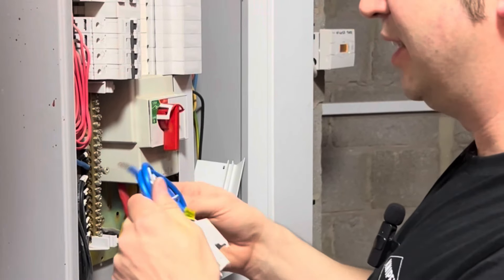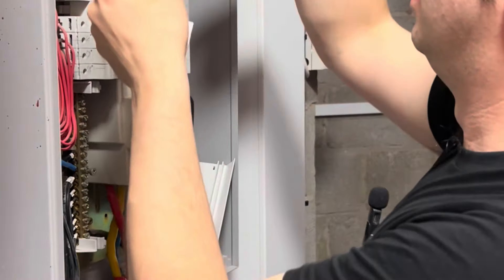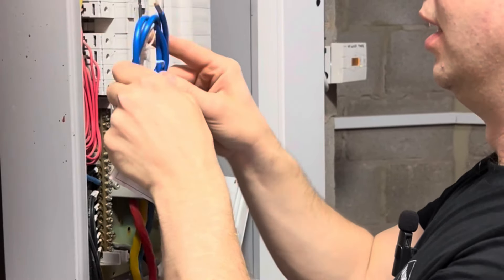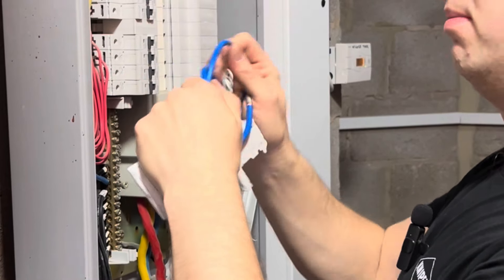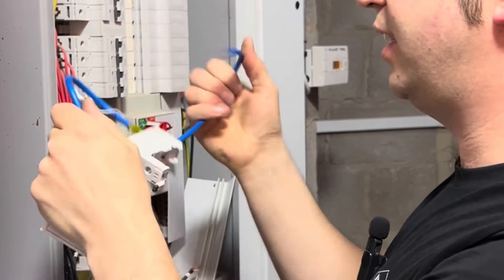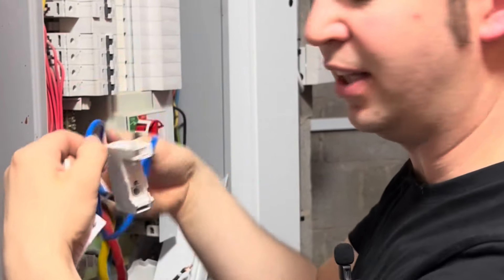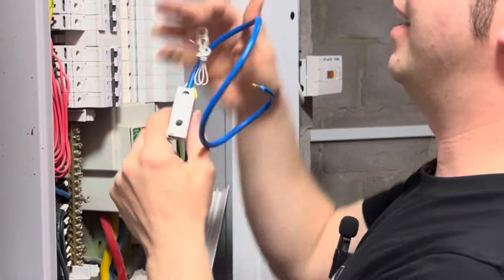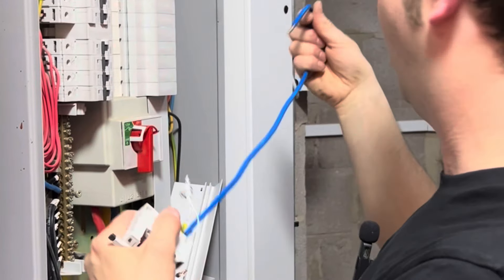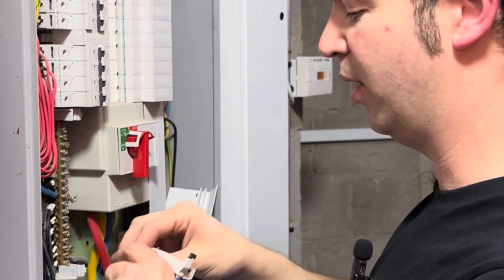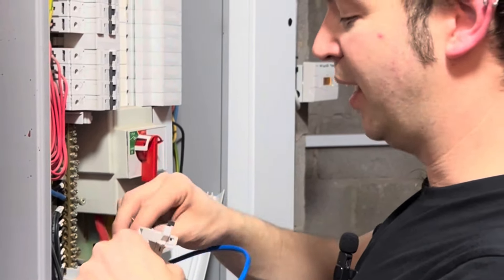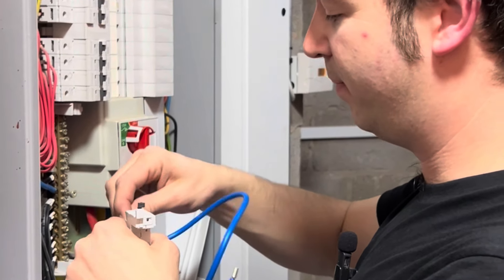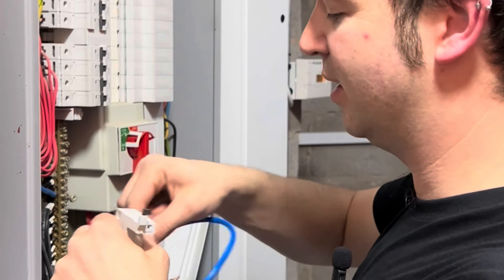The reason for that is that the terminals, like the line terminal, is really far back. Due to the pod arrangement, you actually have to—it's past the clamp, the CT clamp or the CT terminal, the thing that measures the imbalance between the terminals. That's why you can't do it at the terminals. You have to do it at the load. A lot of people, I've had people have questions or other sparkies have said to me when they fitted them, oh I couldn't get a reading at the terminals. That's the reason you can't do it: because the clamp or the CT, whatever you call it, the thing that measures the imbalance, it's really far back due to the pod arrangement.